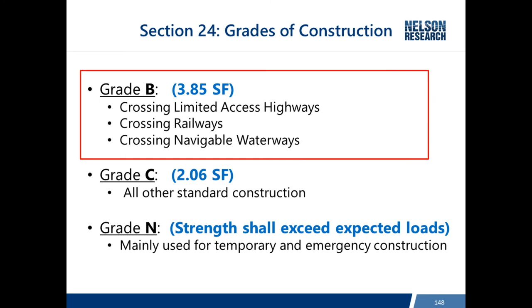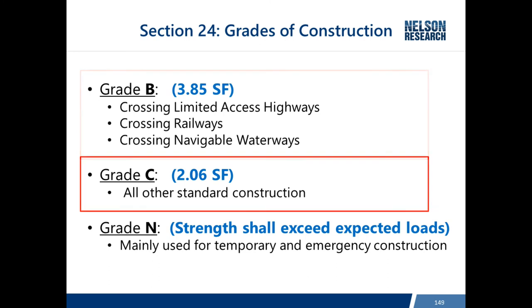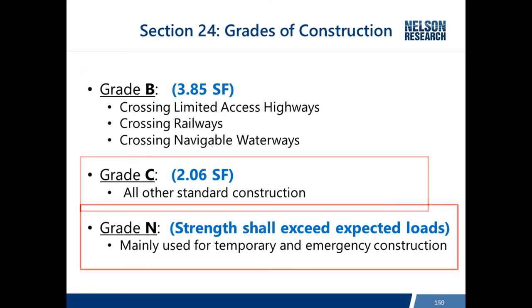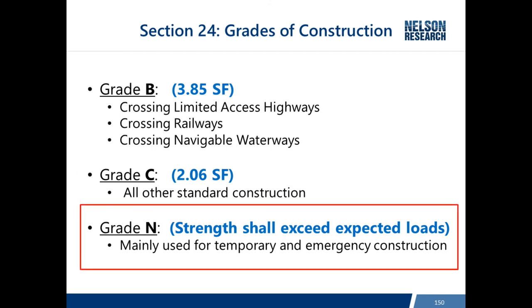Within Section 24, there are three grades of construction. Grade B, the highest grade, is only required if you're crossing limited-access highways, railways, or navigable waterways. Grade C is applied for all other standard construction, and Grade N is used for emergency or temporary construction — defined as the strength shall exceed expected loads.